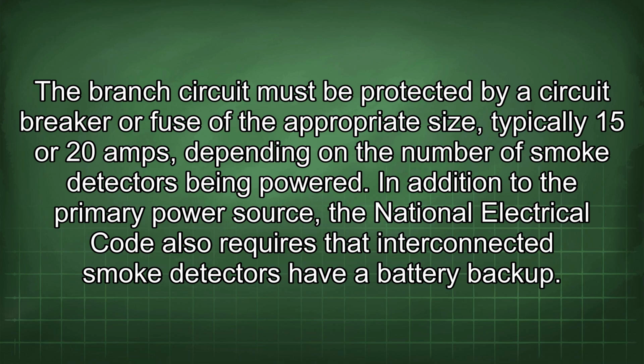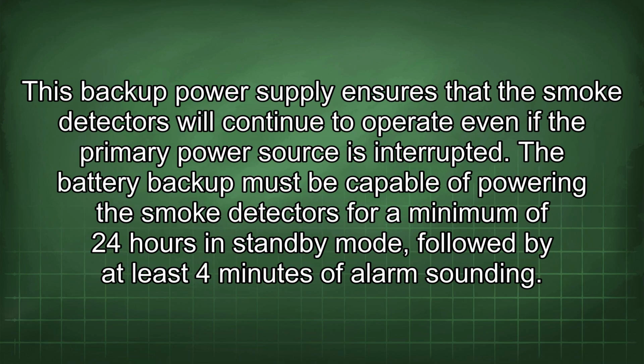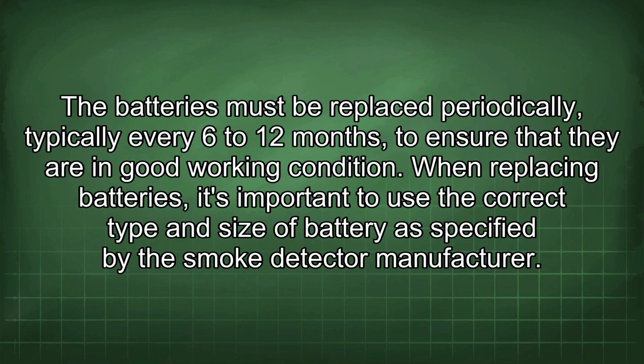In addition to the primary power source, the National Electrical Code also requires that interconnected smoke detectors have a battery backup. This backup power supply ensures that the smoke detectors will continue to operate even if the primary power source is interrupted. The battery backup must be capable of powering the smoke detectors for a minimum of 24 hours in standby mode, followed by at least 4 minutes of alarm sounding. The batteries must be replaced periodically, typically every 6 to 12 months, to ensure that they are in good working condition.